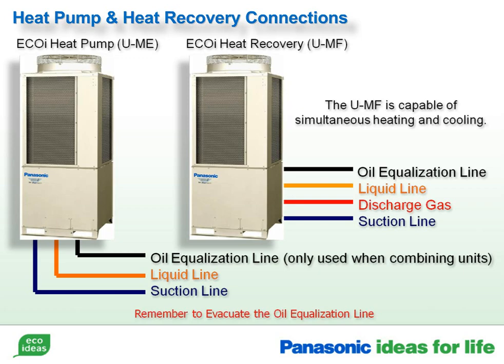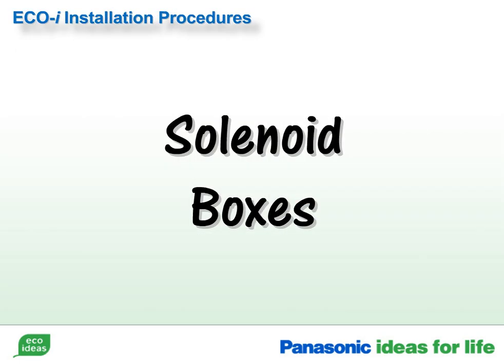The UMF heat recovery unit is capable of simultaneous heating and cooling, which is why you will find that it has a discharge gas line. The oil equalization line is only used when combining condensers. If you are installing a heat recovery system, solenoid boxes must also be installed to provide simultaneous heating and cooling.